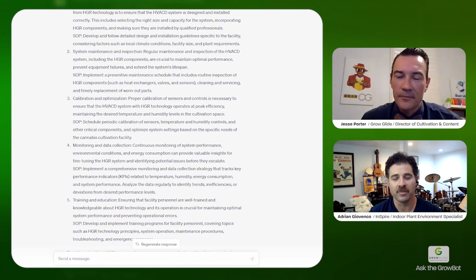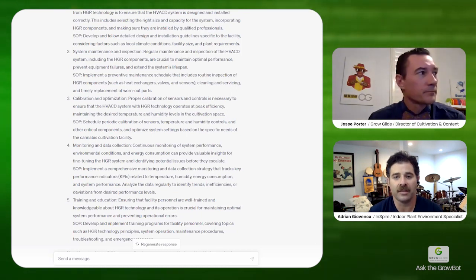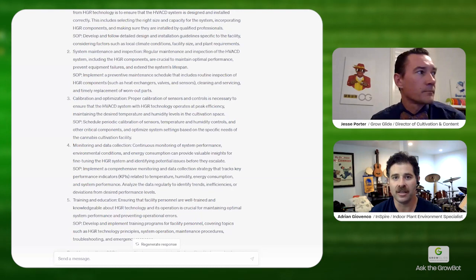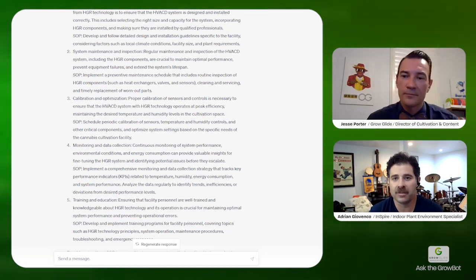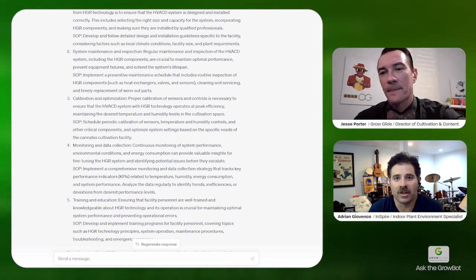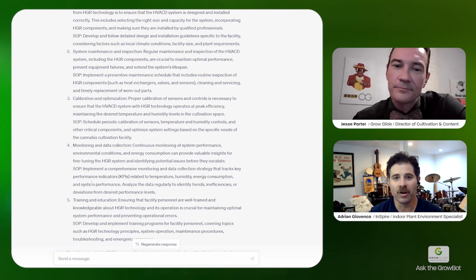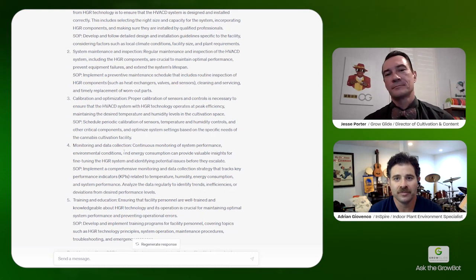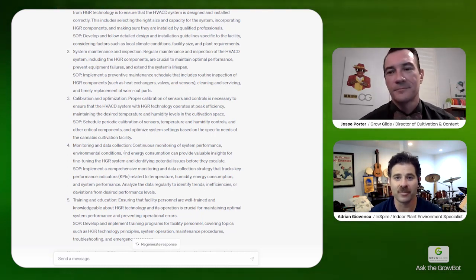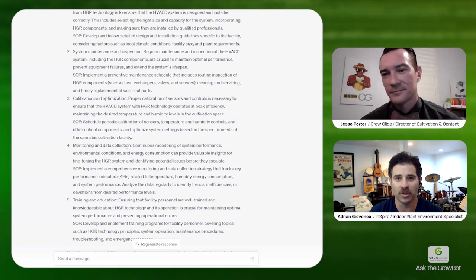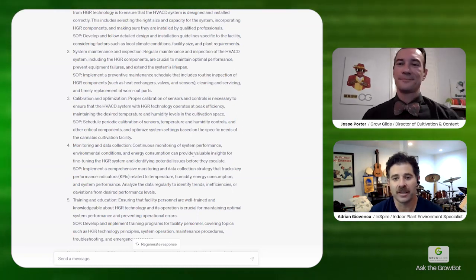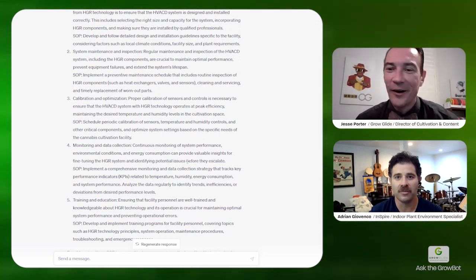Knowing what's happening minute by minute is one of the first places to start. Even outside of that, when they know they have an issue and can't maintain conditions, for us it's always an energy balance equation. What's your water in, what's your lights in? We run the calcs, look at the equipment they have, and figure out what conditions they're trying to maintain. We baseline that with the existing equipment and see if it balances out. If it doesn't, now we know what to target. You're either under on sensible cooling capacity or under on dehumidification capacity. That's really what we see almost across the board, being under on dehumidification.